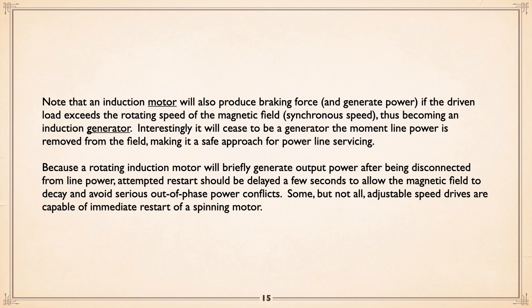Because an induction motor will briefly play generator when it's disconnected from power, a restart of an induction motor should be delayed a few seconds to allow that magnetic field to decay and avoid serious out-of-phase power conflicts. Some, not all, a lot of adjustable speed drives are actually set up so that they can immediately restart into a spinning motor.